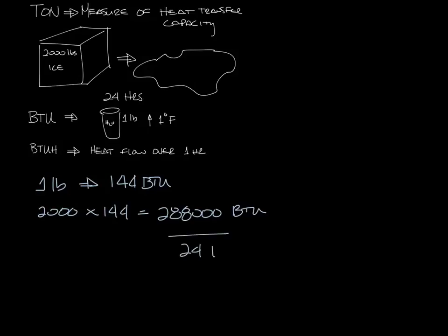So when one pound of ice melts, it absorbs 144 BTU. For 2,000 pounds of ice, it's 2,000 times 144, which is 288,000 BTU. And if you divide that by 24 hours, then you will get 12,000 BTU per hour, or a ton of refrigeration.